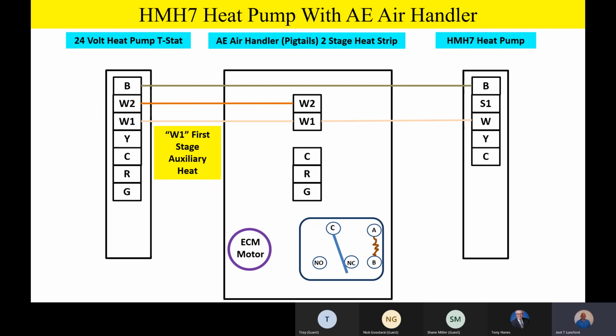Now, please remember that on first stage auxiliary heat, the thermostat can energize first stage auxiliary heat, but also you'll notice on the outdoor unit, we have a W terminal. That's to bring the heat strip on, that first stage of heat strip during defrost. Because remember, team, whenever a heat pump goes into defrost, it goes into the cooling mode of operation to defrost the outdoor coil, and it's going to be blowing cold air in the space. So we bring on some heat strips so we don't freeze the homeowner out, or more specifically, we're tempering that air in the defrost mode of operation.